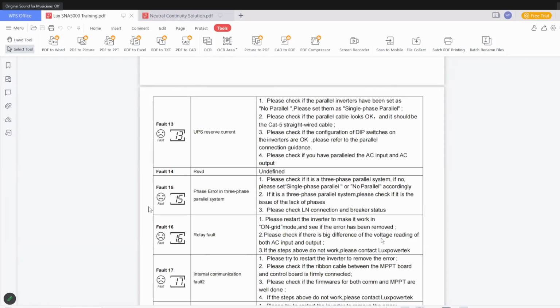Going back to firmware updates, if you try to do them and it keeps failing and you keep retrying, it can cause an internal communication fault. Previously, we used a manual way of doing firmware updates where you'd choose the firmware file, upload it to the system, and then perform the update. That also used to cause internal communication faults if the client selected the wrong firmware.